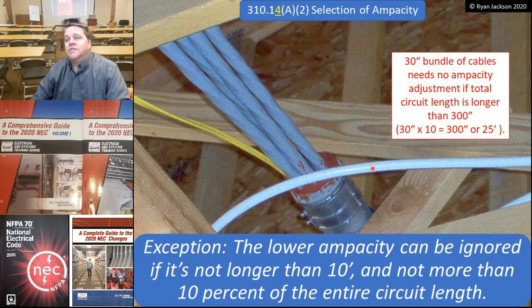Here's a very nice exception though. It says the lower ampacity can be ignored if it's not longer than 10 feet in length and not more than 10% of the entire circuit length.